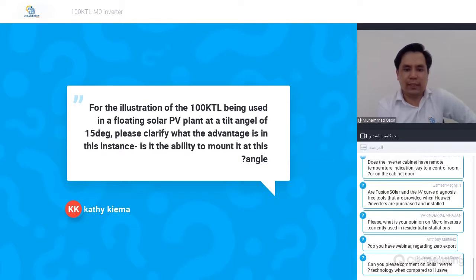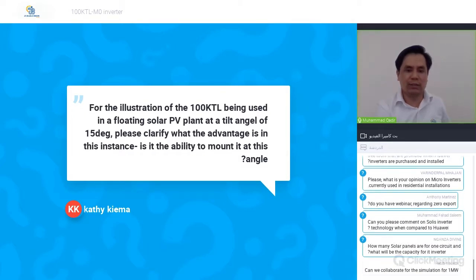For the illustration of the 100 KTL being used in a floating solar PV plant at a tilt angle of 15 degrees, please clarify what is the advantage in this instance? Is it the ability to mount it at this angle? Good question, which I also tried to explain during the same slide. When you are tilting an inverter, let's suppose at a 90 degree angle, it will cast more shadow on the back side. If you are installing the inverter at a lower angle, let's say in this scenario 15 degrees, there would be very small shade on the back side of the inverter. So you have more area to install the solar panels as well. The main purpose is to decrease the shadow on the back side of the inverter and utilize more space.